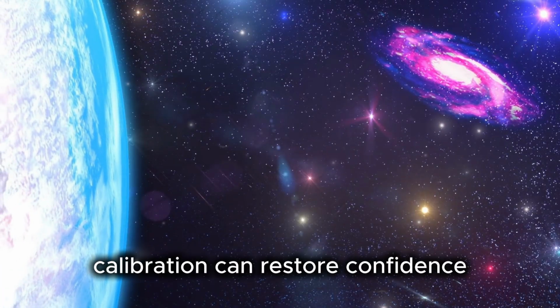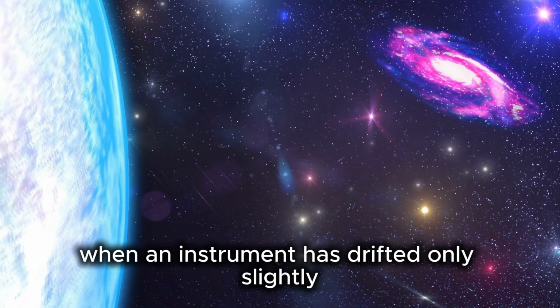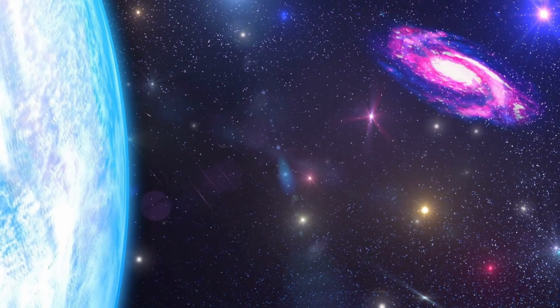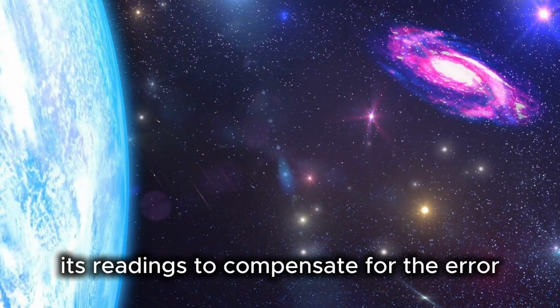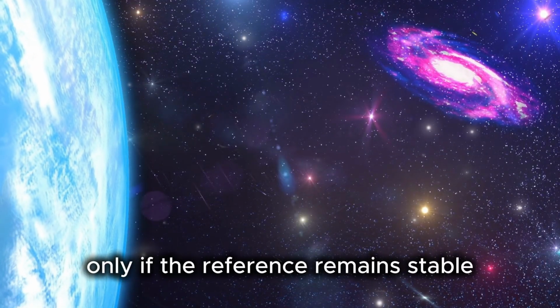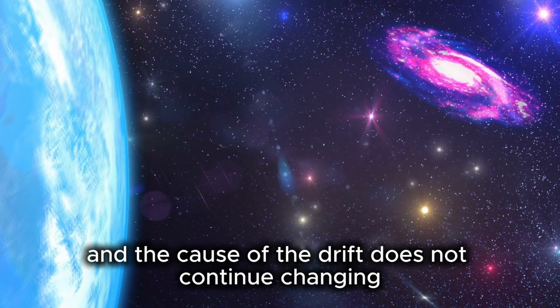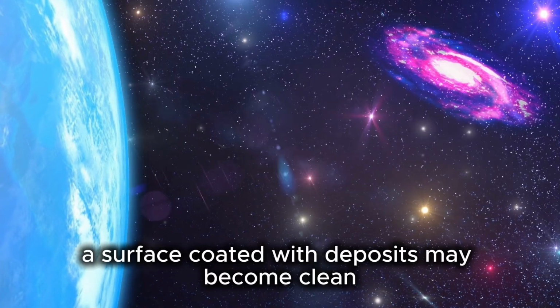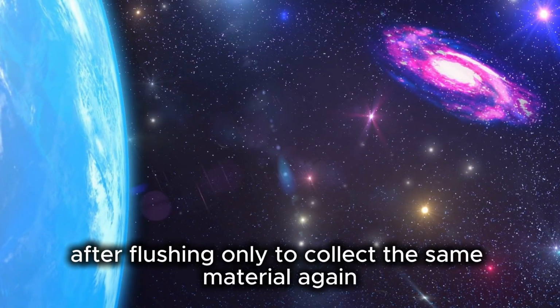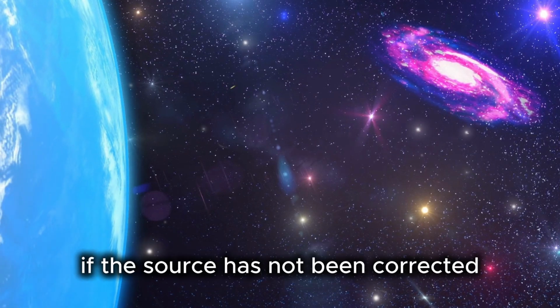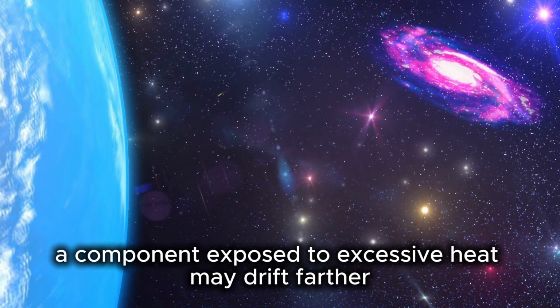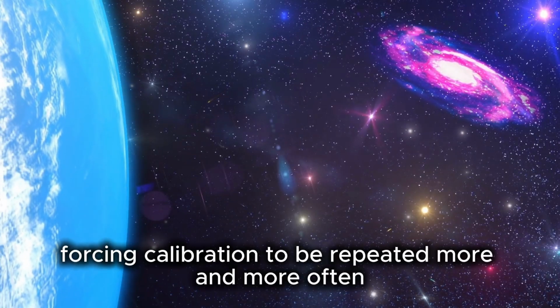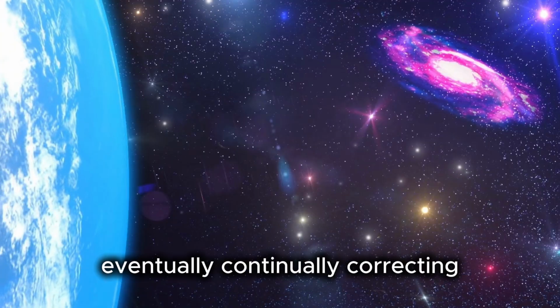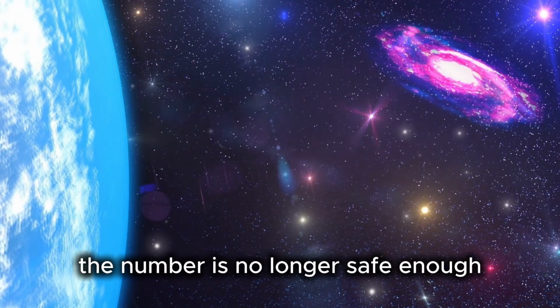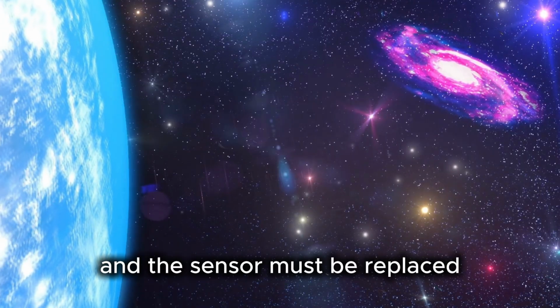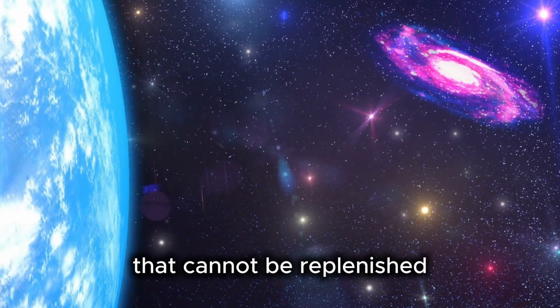Calibration can restore confidence when an instrument has drifted only slightly. The sensor is compared with a known reference, and the software adjusts its readings to compensate for the error. This process is accurate only if the reference remains stable and the cause of the drift does not continue changing. A surface coated with deposits may become clean after flushing, only to collect the same material again if the source has not been corrected. A component exposed to excessive heat may drift farther each week, forcing calibration to be repeated more and more often. Eventually, continually correcting the number is no longer safe enough, and the sensor must be replaced. But that decision still consumes a spare part that cannot be replenished.